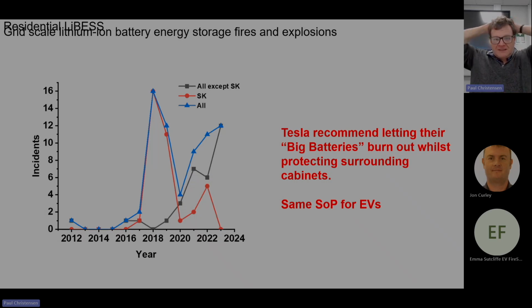Now, there's been about 60 battery energy storage system fires. Essentially, because you cannot get the suppressant and water remains the best of the bad suppressants to the actual cells in thermal runaway and to stop thermal propagation, increasingly the standard operating procedure is to let it burn.